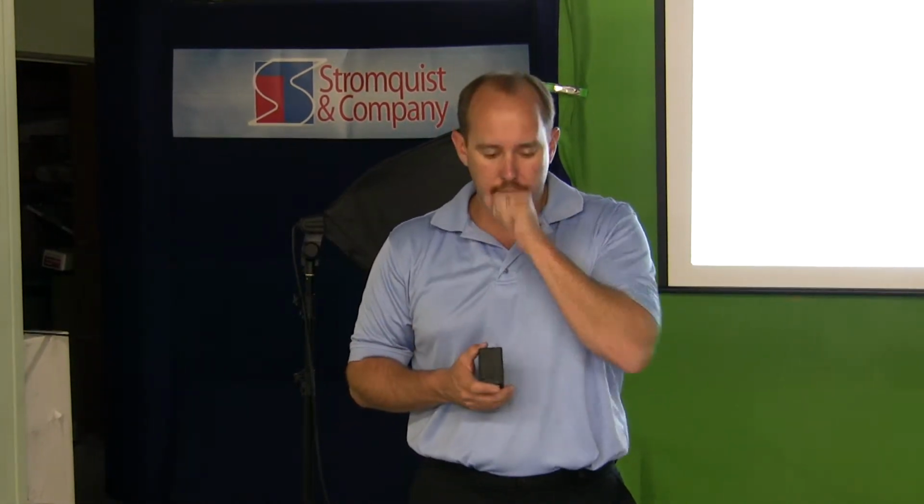A ton of things from the input side, on the alarm inputs, being able to use it for, as I said, occupancy sensor. You can bring in a security alarm to it. So instead of setting a schedule, you can bring an input from your alarm system into us, and when it's activated, it will then put our unit into setback mode, and then take it out of setback mode for you. So you don't have to have a schedule necessarily.